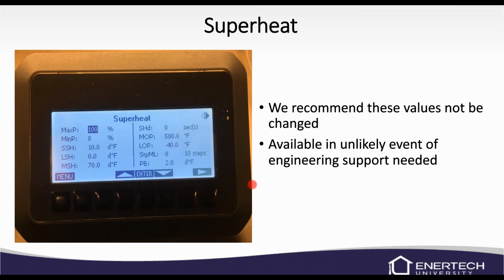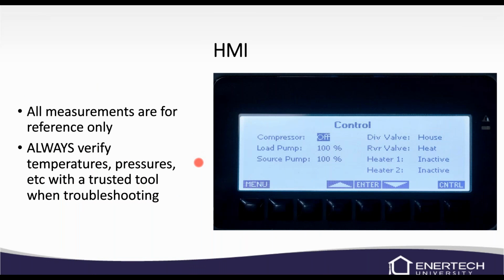Superheat menu, again, you can change these values. I do not recommend it. If you think that you need to change any of these, before doing that, it's recommended that you call tech support, and we'll talk to the engineers and get their take on it. Again, on the HMI, the measurements are for reference only. So always verify with trusted tools such as temperature and pressure gauges, things like that. Make sure you're always double checking with your trusted tools.